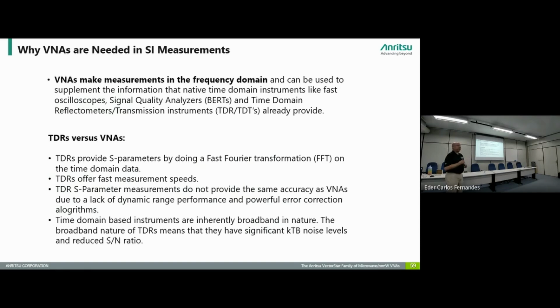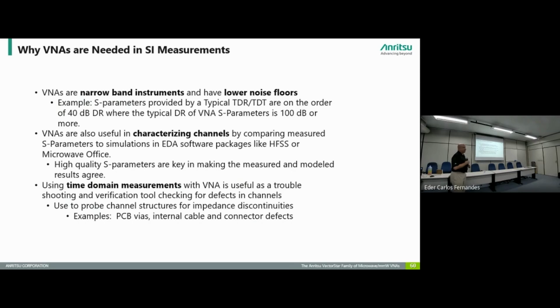So TDRs, most of us are familiar, are time domain instruments. They apply a very fast pulse, and then there's a signal reflected back, and they're good for measuring where there are discontinuities on a line. We can essentially set up the same kind of measurement from the frequency domain by doing an inverse FFT. And so we're going to use time domain to emulate the same capability, but from the frequency domain side. The problem with the time domain instruments is they're a bit limited in dynamic range. So we intend to overcome that by using our VNA that has a lot more dynamic range and a lower noise floor. So how do we do that? How do we get a lower noise floor? We get a lower noise floor through the VNA receiver, which is inherently narrow band, where the scope or the TDR is wideband. The VNA is a narrow band instrument, so we can control our noise floor and our dynamic range and get better accuracy.